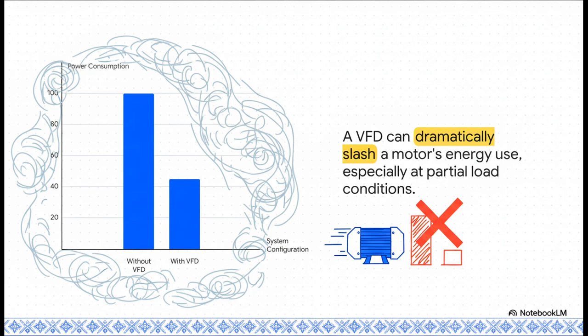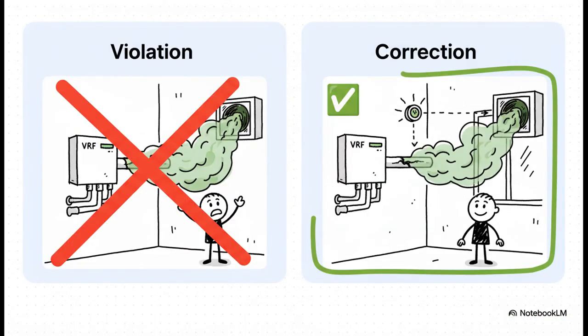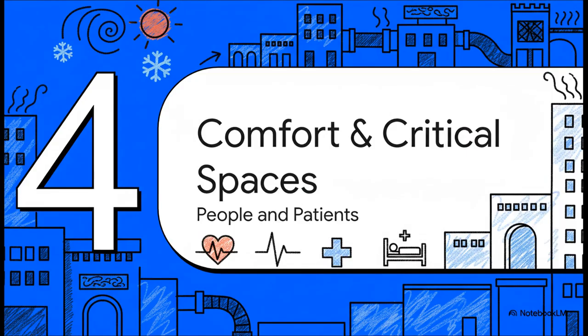This visual right here is why an energy auditor will fail a system without a VFD on the spot. Now for a critical safety point. VRF systems are everywhere, but they use a lot of refrigerant. If you get a leak in a small enclosed room, that's a serious hazard. That's why ASHRAE 15 and 34 require a dedicated gas detector, and it has to be wired to automatically turn on an emergency exhaust fan. An inspector will physically test that connection. No excuses. Okay, let's move on to comfort and critical spaces.